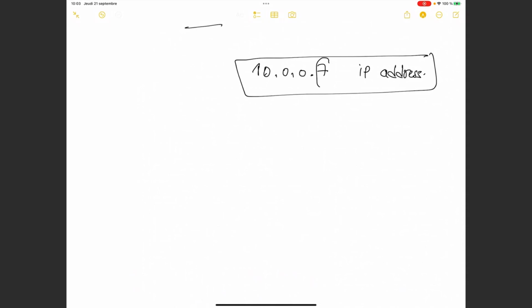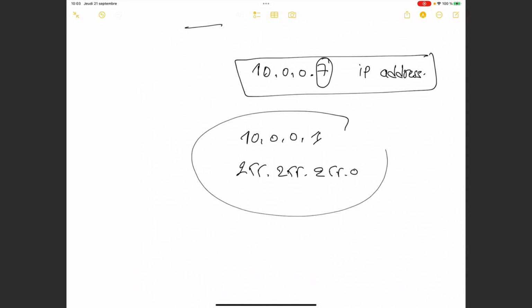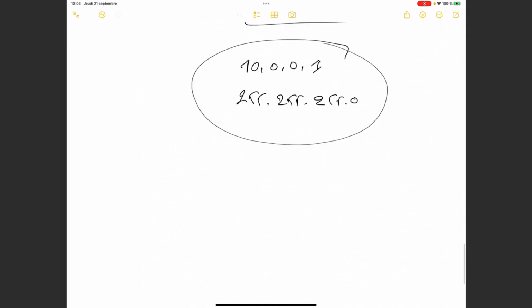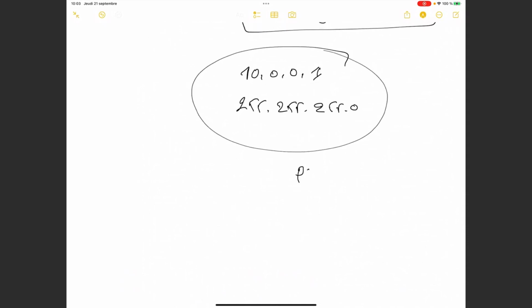All right. So for the connection, I told you always 10.0.0.7. This is the IP address of the analyzer. So you can use any address you want except 7. By default you can use 10.0.0.1, for example, and the subnet mask 255.255.255.0. How to test if the communication is good? You can use ping directly, ping 10.0.0.7 and see if the instrument replies to you or not.